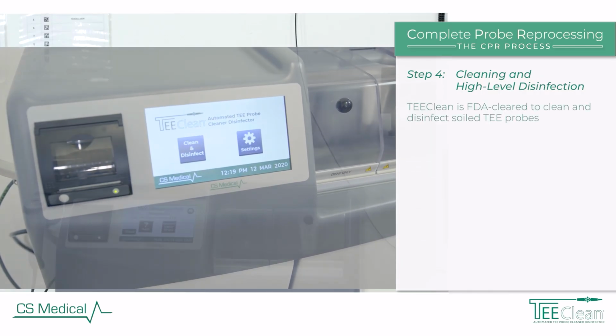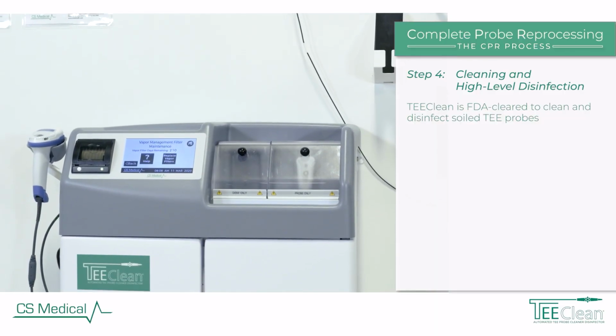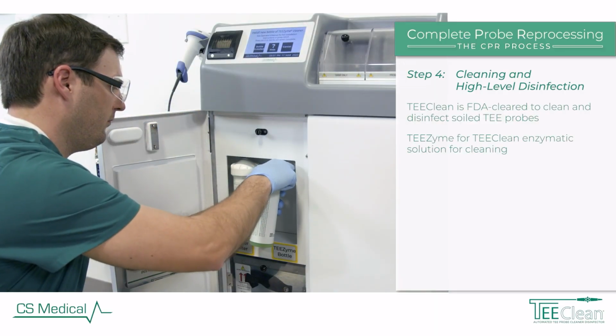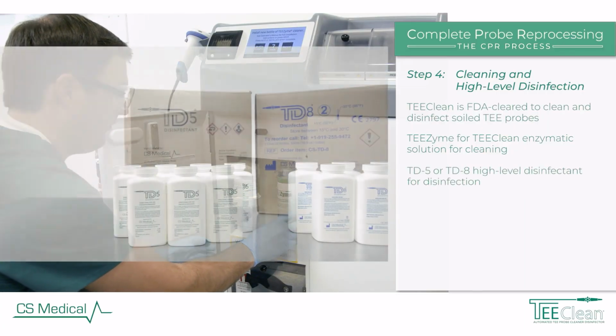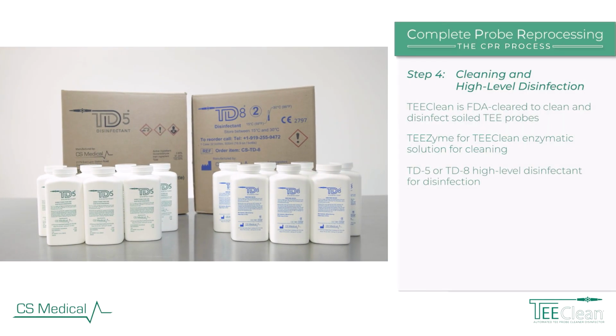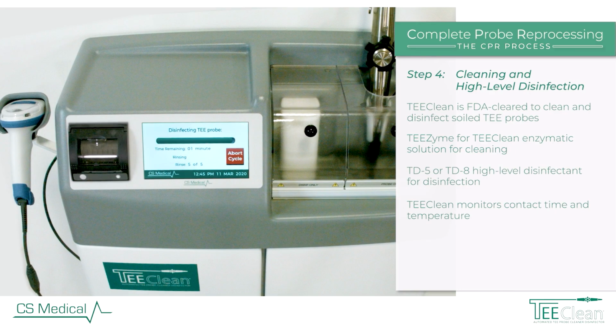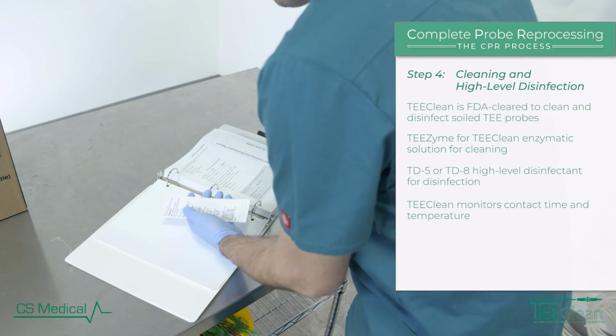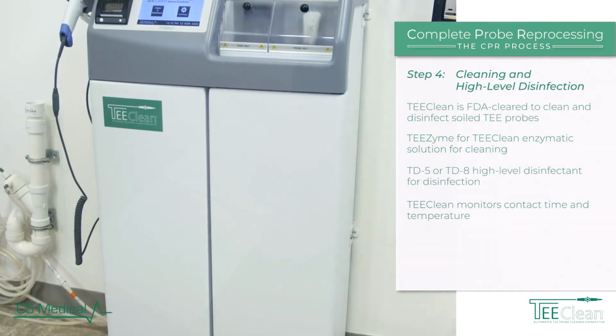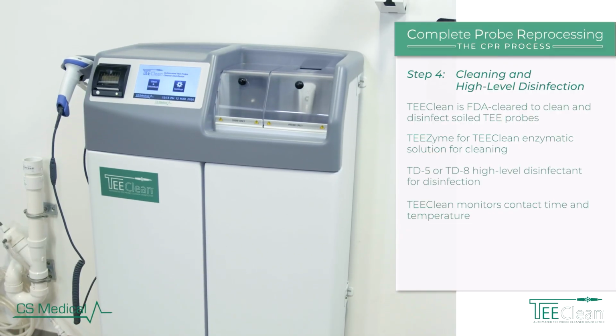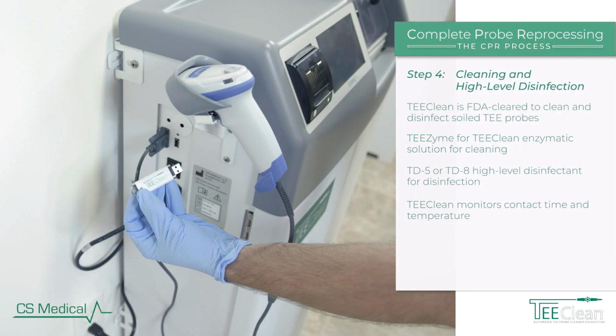Step 4. Cleaning and high-level disinfection. TEEClean is FDA cleared to clean and disinfect soiled TEE probes. TEEClean uses TEEZyme enzymatic solution for cleaning and either TD5 or TD8 high-level disinfectant for disinfection. During the cleaning and disinfection processes, your TEEClean monitors contact time and temperature, ensuring proper cleaning and disinfection. At the conclusion of a successful cycle, a verification report is generated and can be logged in the TEEClean logbook for later reference. An electronic record is saved in system memory for later recall to the built-in printer or exported to the supplied USB for download and transfer to a computer.